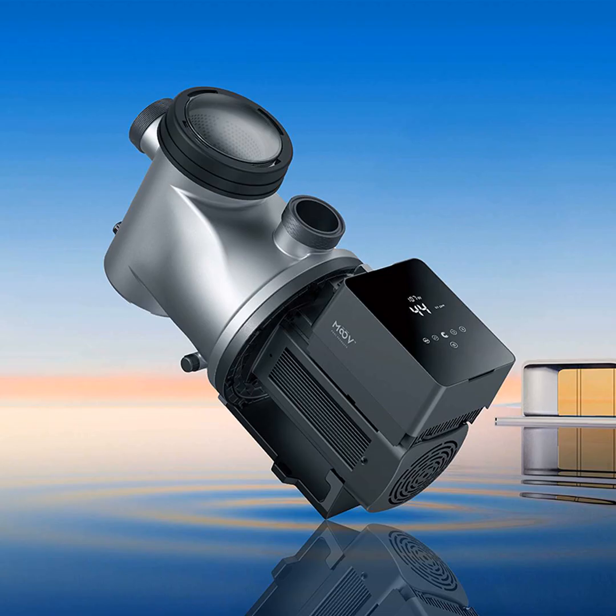The pump would recognize that and then automatically adjust its speed. So it is a variable speed pump that you can control by any other system like a percentage. And you can also control this product by flow control, which is basically setting a required flow, potentially at 80 GPM, where your waterfall looks nice and all the other features on the pool look nice.